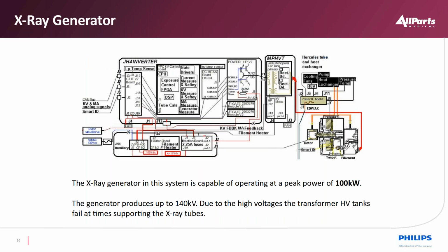This is showing an X-ray generator from the VCT. We have the inverter driving a high voltage tank, and that is a tuned circuit. By tuning the circuit, we can control the frequency that drives the high voltage tank, and that will control the kilovolts, or kV. So we're dealing with up to 140,000 volts. Then we also have pump circuits and rotor circuits to spin the anode target. And the filament is what we use to control the mA. So as you can tell, we have a lot of processes wrapped around the X-ray tube as well.